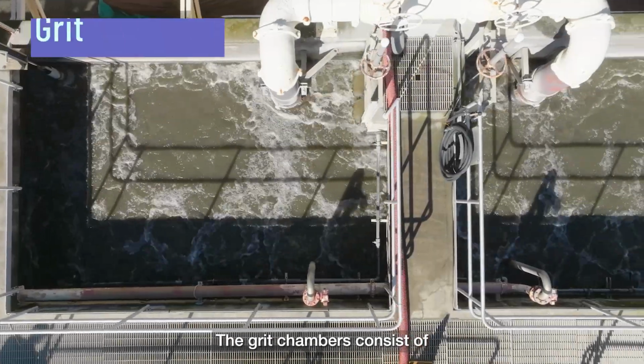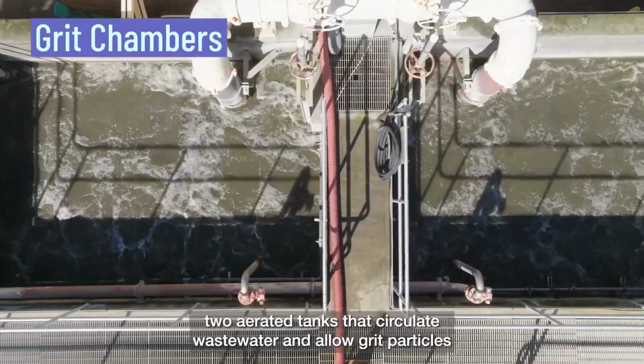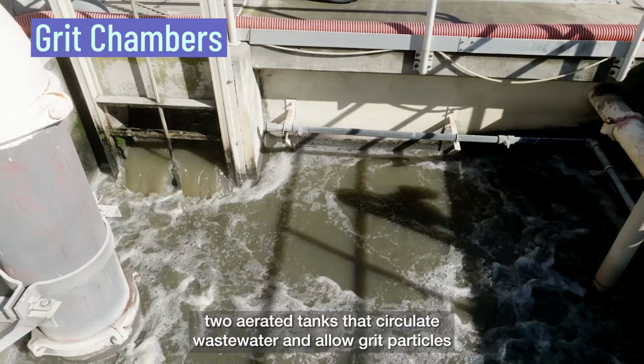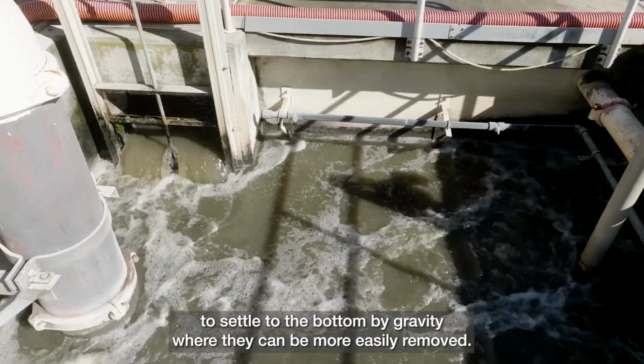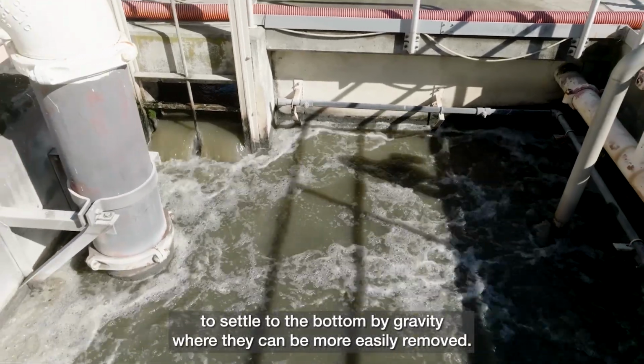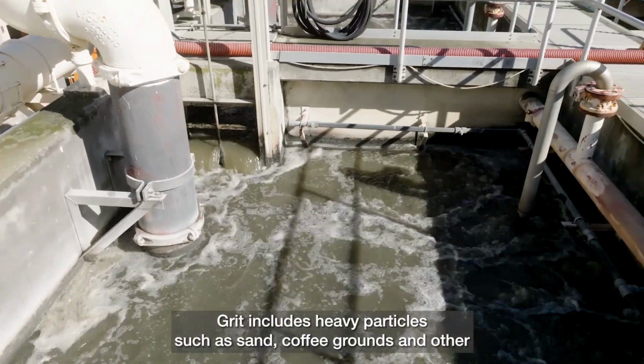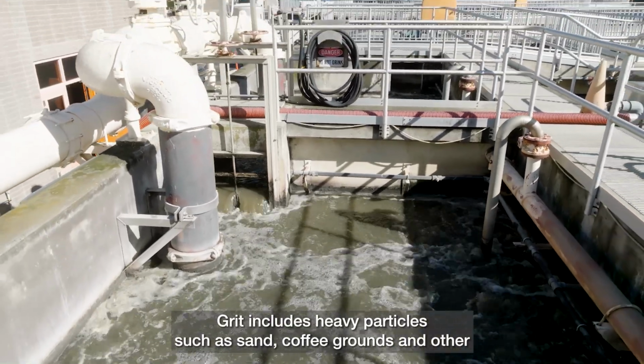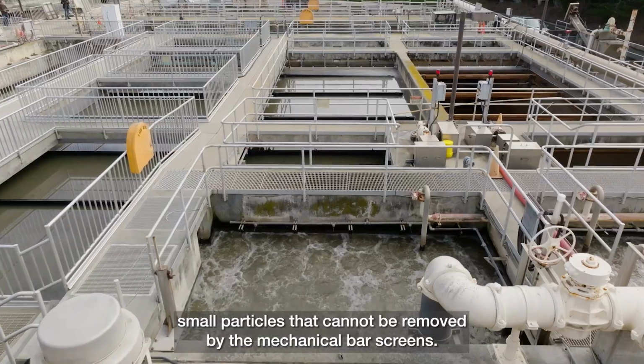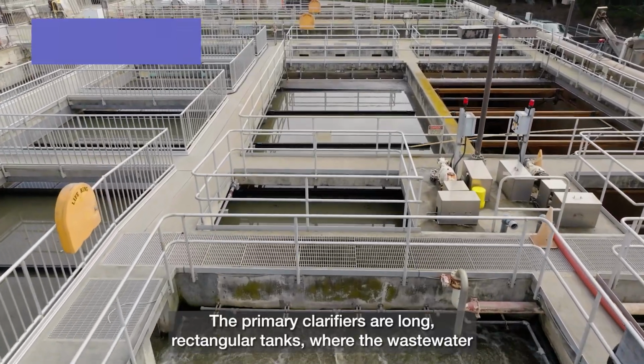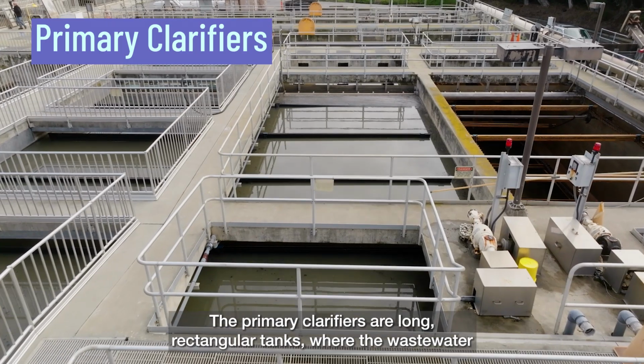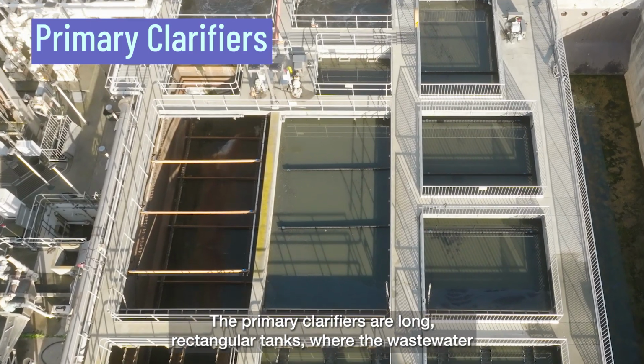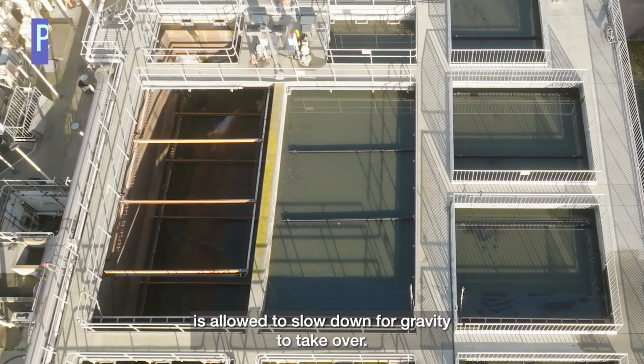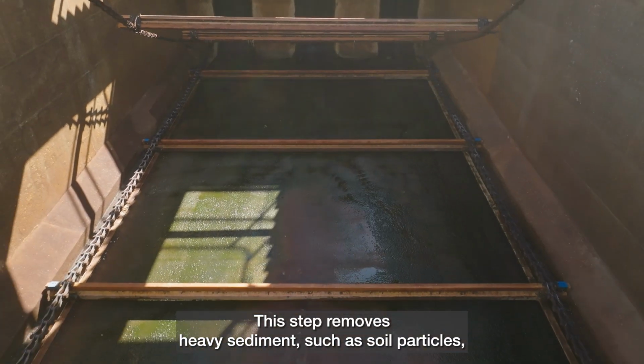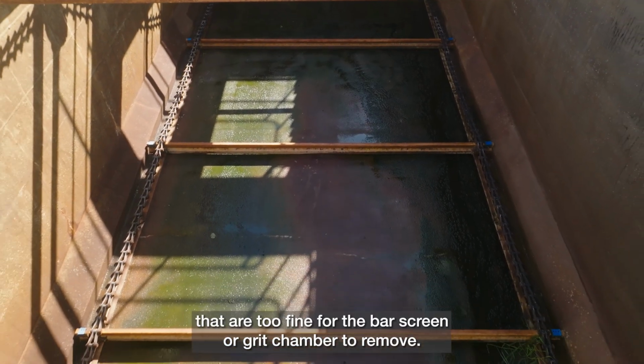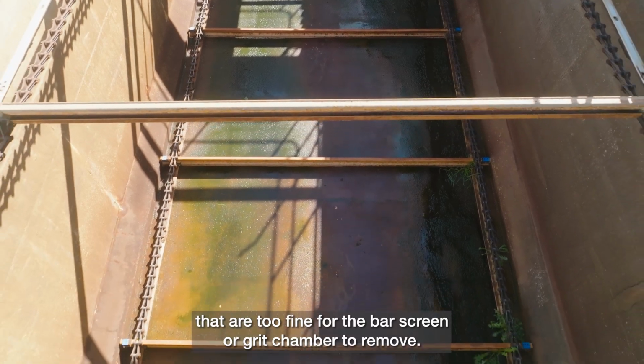The grit chambers consist of 2 aerated tanks that circulate wastewater and allow grit particles to settle to the bottom by gravity, where they can be more easily removed. Grit includes heavy particles such as sand, coffee grounds, and other small particles that cannot be removed by the mechanical bar screens. The primary clarifiers are long rectangular tanks where the wastewater is allowed to slow down for gravity to take over. This step removes heavy sediment, such as soil particles, that are too fine for the bar screen or grit chamber to remove.